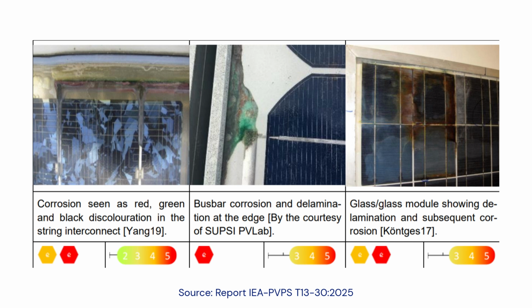Dark areas at the cell borders of the electroluminescence images can here highlight the diffusion of moisture through the rear side of the module and the gaps between the cells and the subsequent front side cell corrosion starting from the edges. The oxidation of the metallization is caused by the presence of moisture and acidity in the encapsulant, as for example acetic acid, a degradation product of the mostly used encapsulant ethylene vinyl acetate, or remaining crosslinker, peroxides. Acetic acid has a corrosive effect on the cell metallization and the cell interconnect.